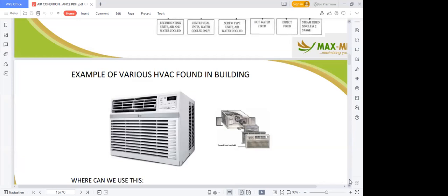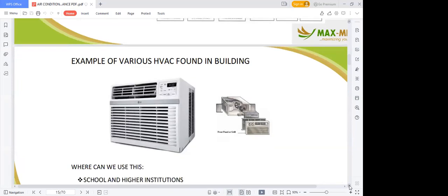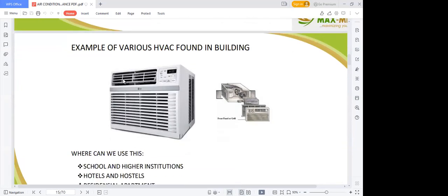Then this is the window type I talked about. You see how big it is. So this area is the cooling, and this is the return air. In order to identify the return air, you can use a small paper. Once you put a small paper within this place, you discover that this part is actually sucking. So anywhere you see the unit suck, that is where the filters are always installed. Once you remove this front grill, you are going to see the filter installed here.